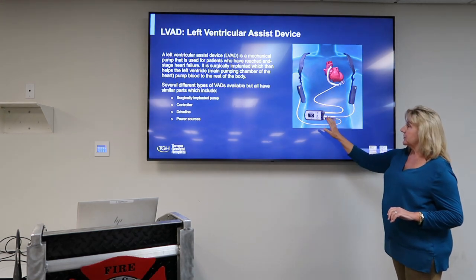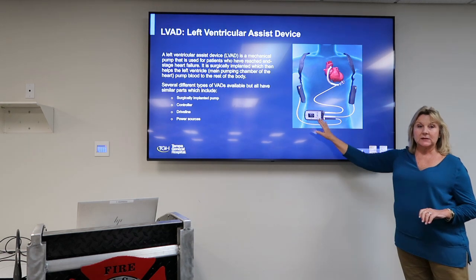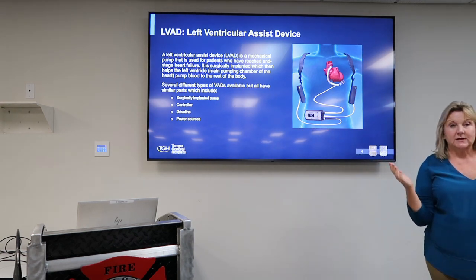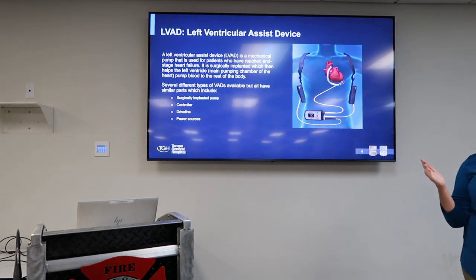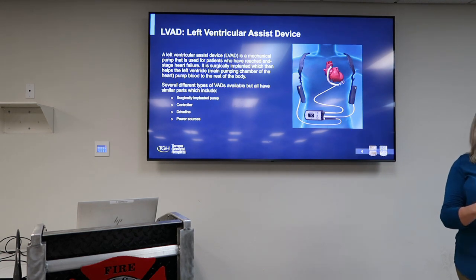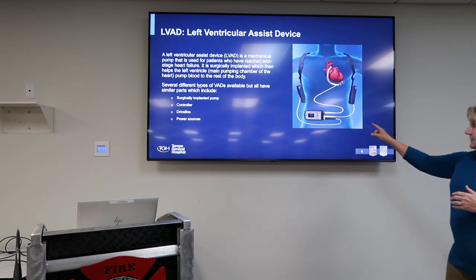From here, these devices are attached to an outside controller, the microprocessor, the brains of the system. The controller stores the settings of the pump, monitors the pump, and if there is an alarm state, it gives a signal on that little LED screen that tells the patient or caregiver what's wrong and what to do about it.